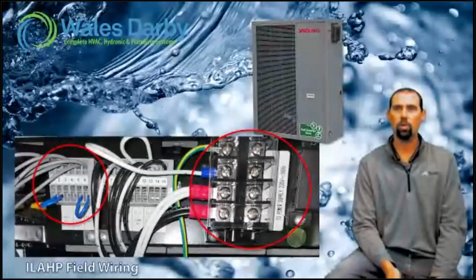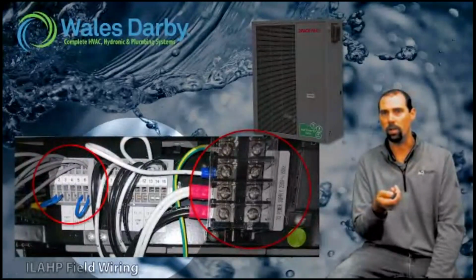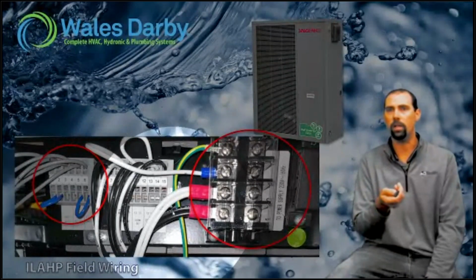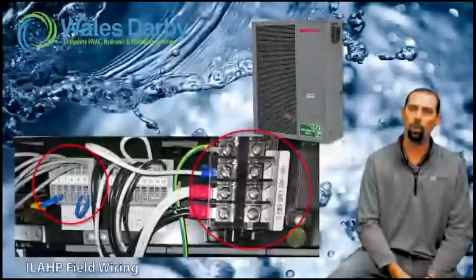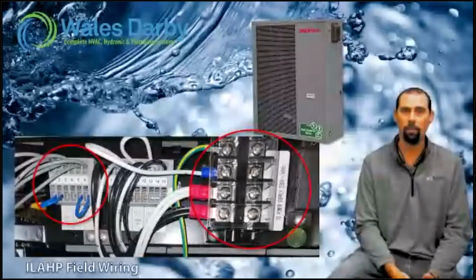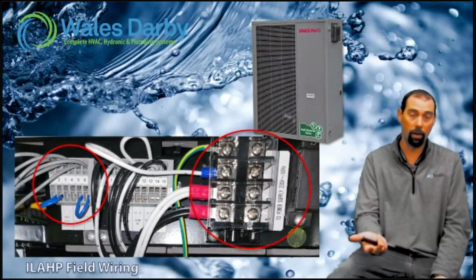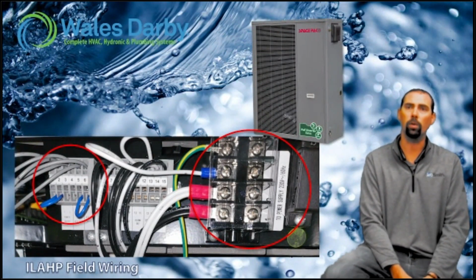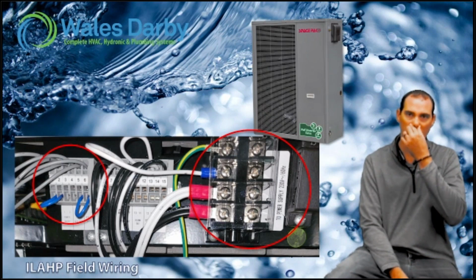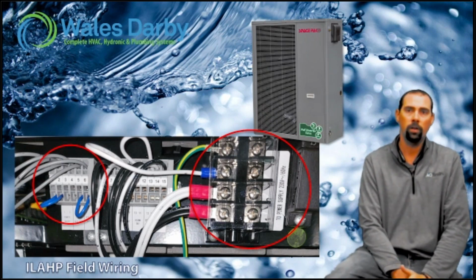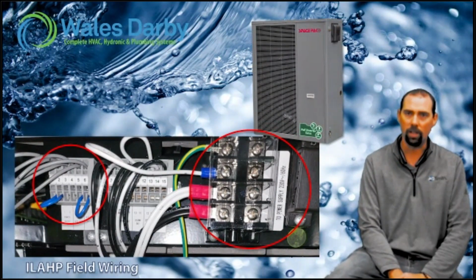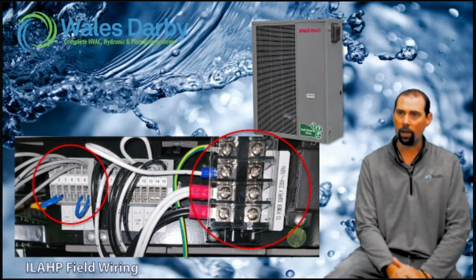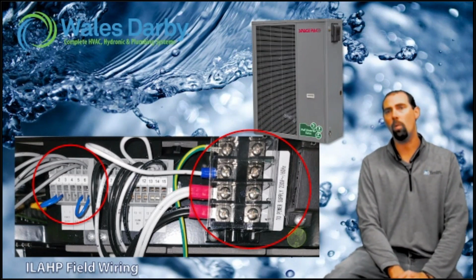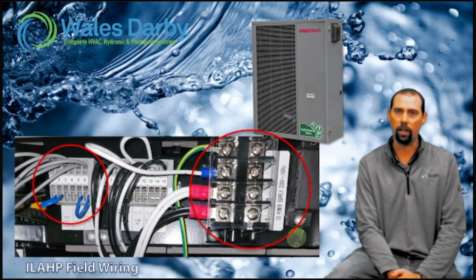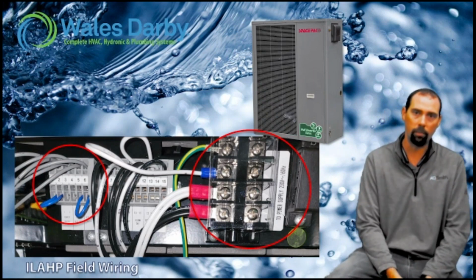Right? So we bring in a neutral because behind this little bundle, and I didn't circle it because we can't really see it, there are some circulator terminals. So we power our circulator for our heat pump directly off of the heat pump itself. So we need that neutral there and a 120 leg. That's already pre-wired into the system. You're just making your connections there, running them into the building. So there is some wiring going on there. Like I said, if you're doing your own wiring, this is very easy. If you get an electrician in there, it should be very easy for them to follow.